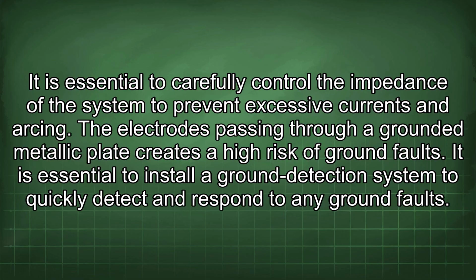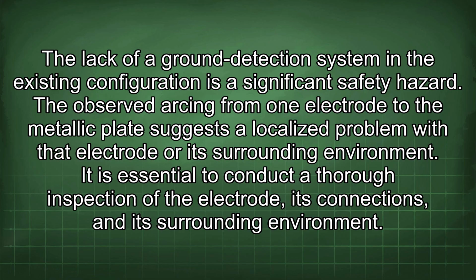The electrodes passing through a grounded metallic plate creates a high risk of ground faults. It is essential to install a ground detection system to quickly detect and respond to any ground faults. The lack of a ground detection system in the existing configuration is a significant safety hazard.